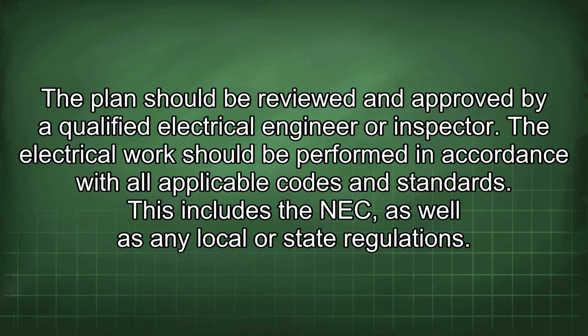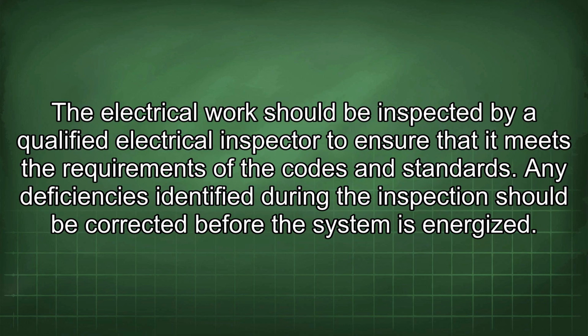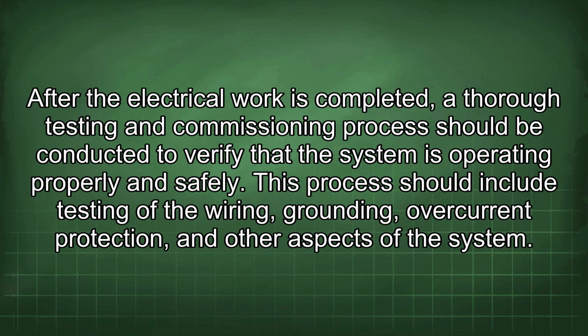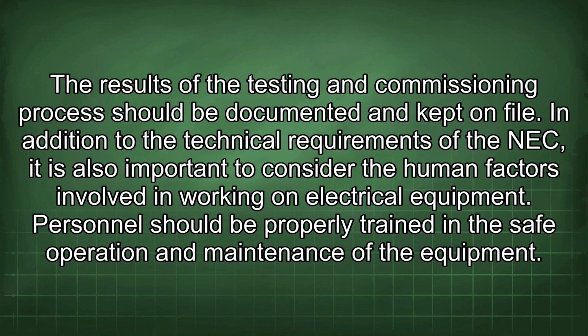The electrical work should be performed in accordance with all applicable codes and standards. This includes the NEC as well as any local or state regulations. The electrical work should be inspected by a qualified electrical inspector to ensure that it meets the requirements of the codes and standards. Any deficiencies identified during the inspection should be corrected before the system is energized. After the electrical work is completed, a thorough testing and commissioning process should be conducted to verify that the system is operating properly and safely. This process should include testing of the wiring, grounding, overcurrent protection, and other aspects of the system. The results of the testing and commissioning process should be documented and kept on file.